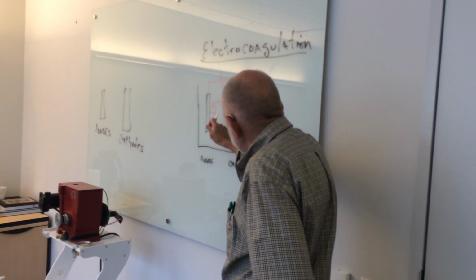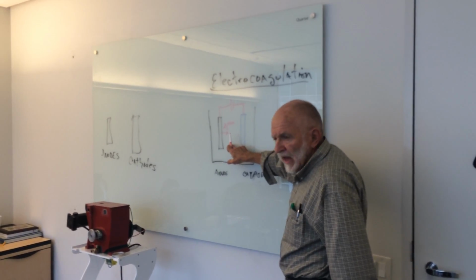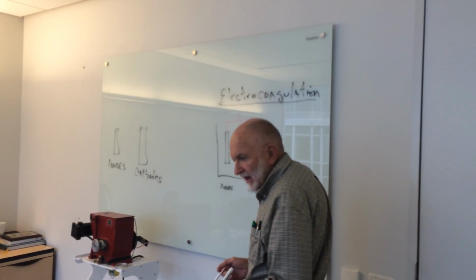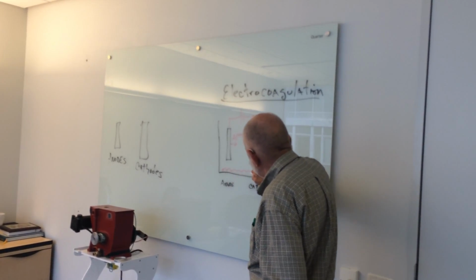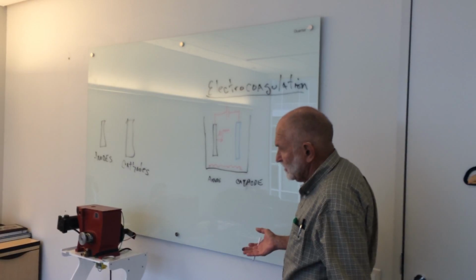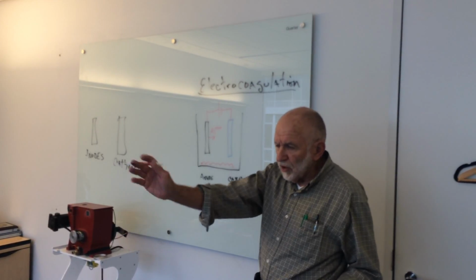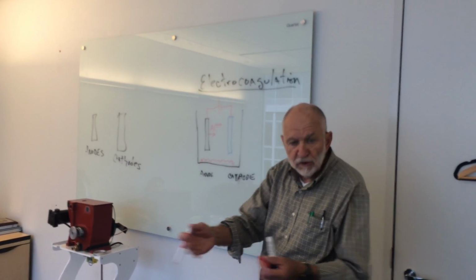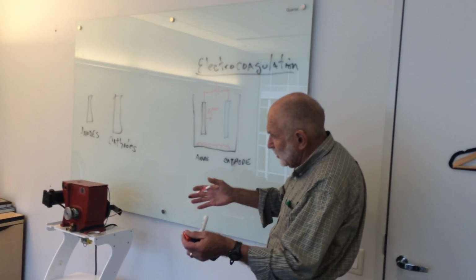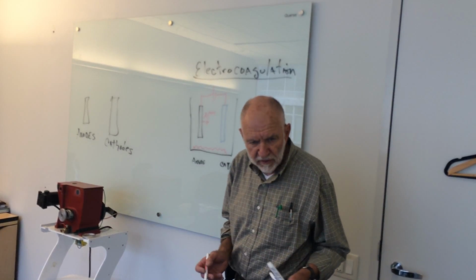But at any rate, no matter what's in the water, with the exception of salt, this reacts, creates a chemical compound, and it does one of two things. It either settles out or it rises to the top. You wind up with a precipitate down here that's completely inert. You can put it in a landfill with no trouble at all. Typically in a continuous run, you let the water go into a flocculation tank for just a few minutes, and then you filter. That's how you run the operation.